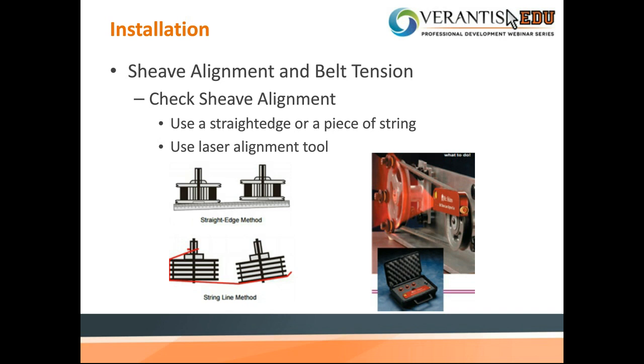Now, the most common is the straight edge or the string method, which is basically when you lay a straight edge or a piece of string over the two pulleys, each of the pulleys should touch in two different locations, on the left-hand and the right-hand side. If you look at the picture in the top, the straight edge method, you'll see there's a little gap underneath the second pulley, the right-hand pulley. So that straight edge is not connecting on 4 different points. It looks like it's connecting on 2 on the first one, and then 1 point on the left and 1 on the right-hand side.